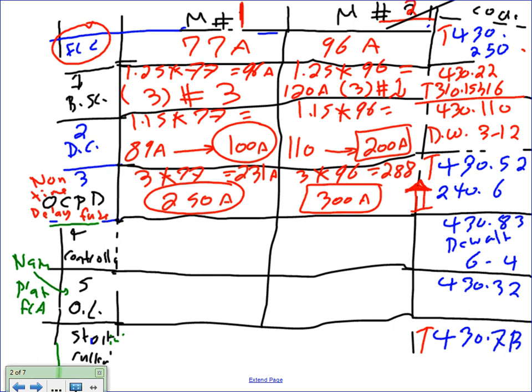On a branch circuit, where do we go if it's not standard? Up, not down. Now, the sheet that you showed me from your company, you know what they did on the branch circuit? They went down. Can I go down if I want to? Yes, please don't do it in the test because I need standardization in the test. When you go to your company, guys, if you find your company is going down on the overcurrent protection device, it's okay. It's not a violation of the code. We're talking about the maximum.